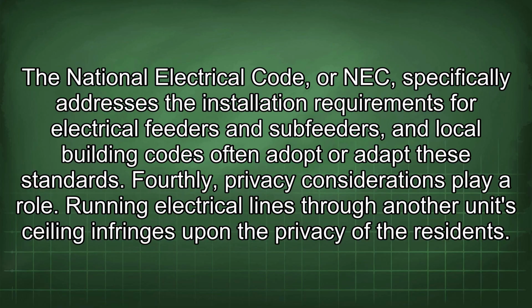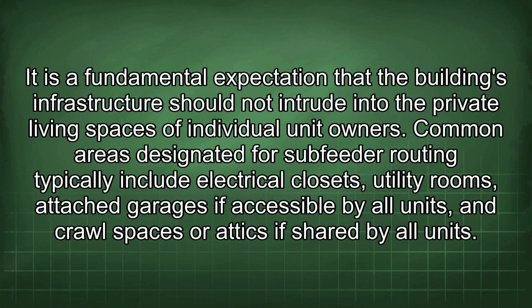Fourthly, privacy considerations play a role. Running electrical lines through another unit's ceiling infringes upon the privacy of the residents. It is a fundamental expectation that the building's infrastructure should not intrude into the private living spaces of individual unit owners. Common areas designated for subfeeder routing typically include electrical closets, utility rooms, attached garages if accessible by all units, and crawl spaces or attics if shared by all units.